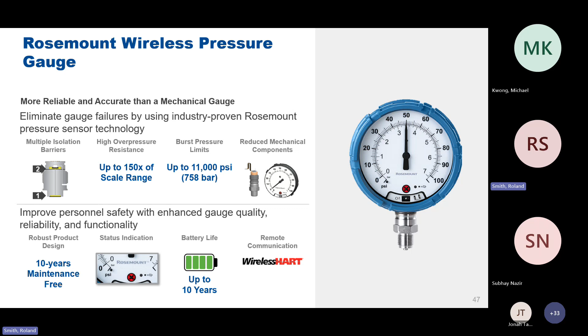So it's isolated with a couple barriers. It's got overpressure protection. There's a lot. I recommend going to the Rosemount YouTube channel for a variety of different reasons. But on there, you will see a wireless pressure gauge where they have a 0 to 5 psi gauge. They're applying 2.5 pounds to it. So the dial is dead center. They overpressure that gauge 3 times to 720 pounds and bring it back to 2.5 psi every time. You can't do that with a mechanical gauge. It simply will not be repeatable after it's overpressured.